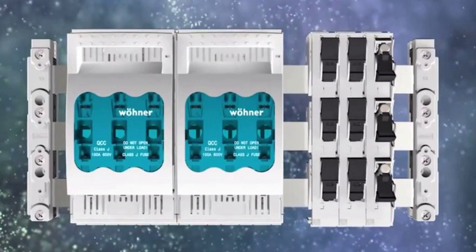Electrical busbar systems can be differentiated by the distance between the center of each busbar and vary according to maximum current carrying capacity of the system, which depends on IEC standards. Commonly known busbar system types: 40 mm busbar system, current carrying capacity up to 300 to 400 amps. 60 mm busbar system, current carrying capacity up to 800 amps. 100 mm busbar system, current carrying capacity up to 1250 amps. 185 mm busbar system, current carrying capacity up to 2500 amps.